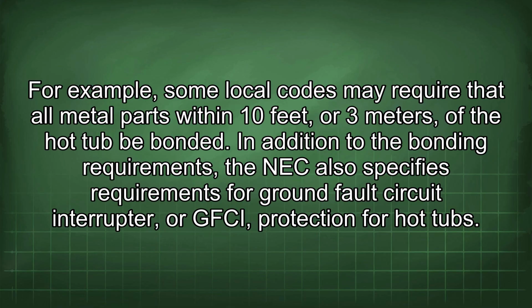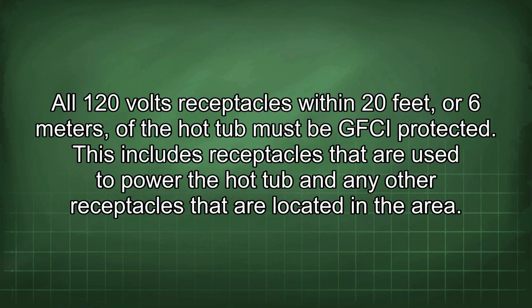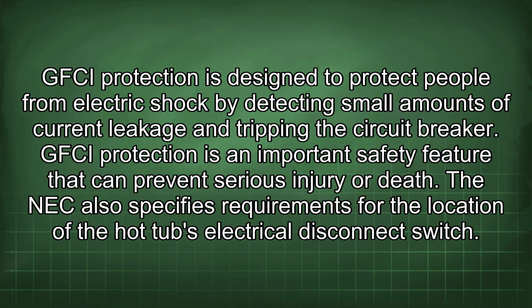In addition to the bonding requirements, the NEC also specifies requirements for ground fault circuit interrupter, or GFCI, protection for hot tubs. All 120 volt receptacles within 20 feet or 6 meters of the hot tub must be GFCI protected. This includes receptacles that are used to power the hot tub and any other receptacles that are located in the area. GFCI protection is designed to protect people from electric shock by detecting small amounts of current leakage and tripping the circuit breaker. GFCI protection is an important safety feature that can prevent serious injury or death.